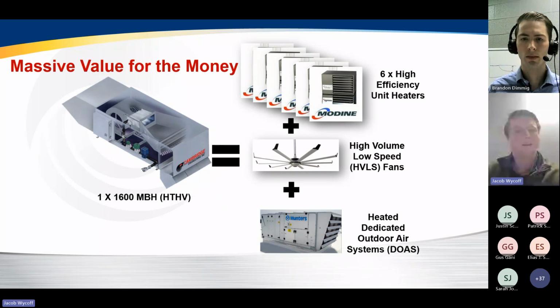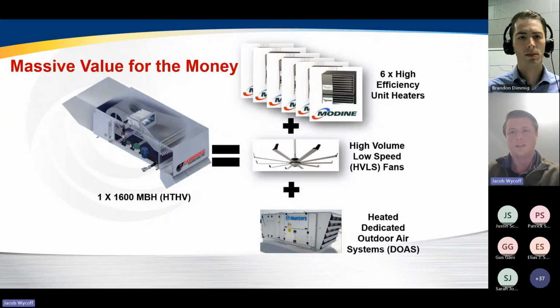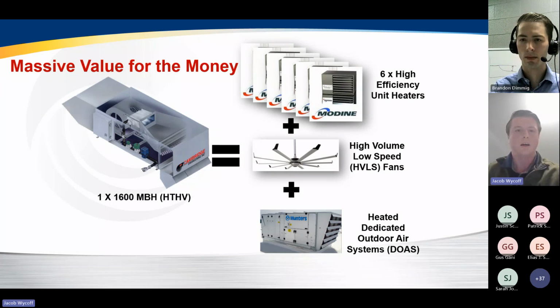So we often get people trying to compare the equipment cost of HTHV versus other equipment like unit heaters. But really the more apt comparison is to compare the total installed cost of an HTHV unit to a similar performing system that would require all of these that you see on the right. When we're talking total installed cost, an HTHV unit is going to have less gas piping, less electrical connections, and less total equipment to install. It will be much simpler, have much more simple controls, and it's going to last for a very long time with very minimal maintenance. Overall, leading to a massive value for the money for the end user over the 20 to 25 year lifespan of the HTHV unit.